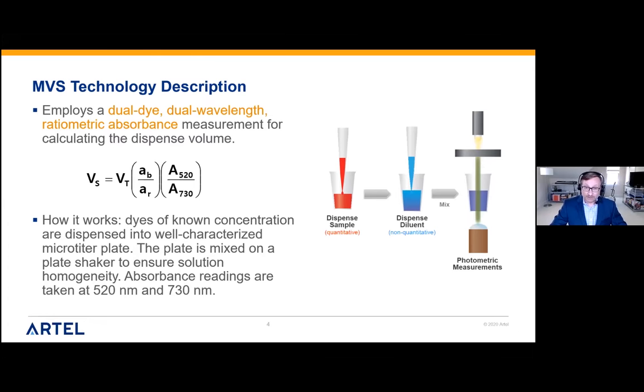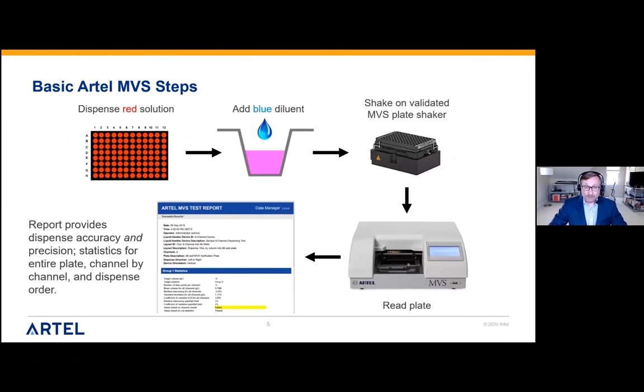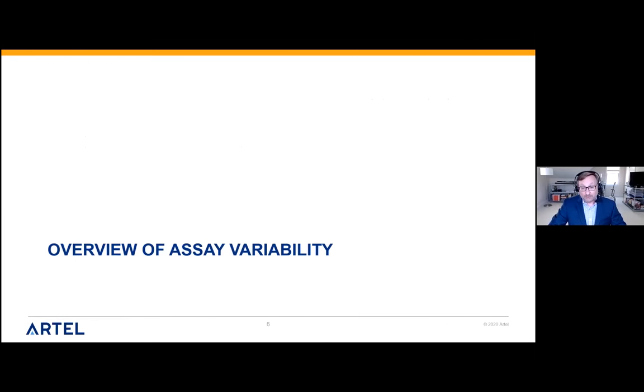This is where people will hear us talk about NIST traceable — a lot of work goes into preparing these reagents to make them NIST traceable. The basic process is: dispense your red solution into a plate, add your blue diluent, use the validated plate shaker, and get a readout and report. That report provides dispense accuracy and precision, which is what most people know us for. We can look at the entire plate channel by channel. But what we want to do is get people thinking more broadly about the assay process, extending this technology to evaluating different parts of the assay.